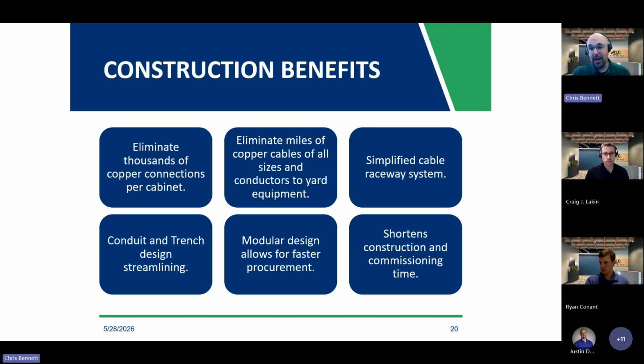Construction, talking about the actual act of putting everything together. As mentioned, every one of those traditional designs needed multiple cables to get the statuses back, the trip signals back, the close signals back, the monitoring signals back, VTs, CTs, power, you name it. That was another cable. So by keeping the cabling local to the device, you're eliminating thousands of copper connections in the cabinets, elimination of 7 cabinets in our example, and the miles of cable that you're going to need to run out to the yard.